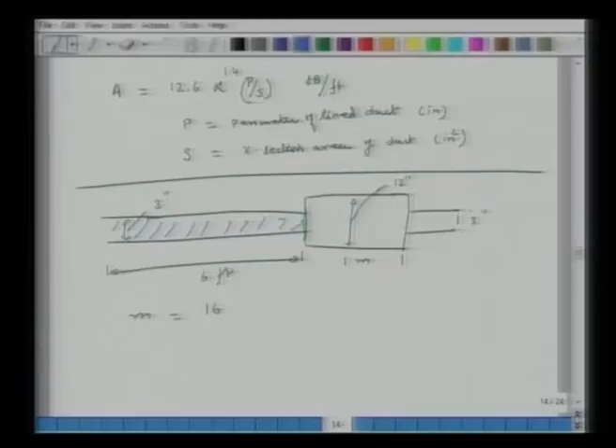So then I said, okay, for comparison purposes, let's say that I line this entire tube with some sort of a highly acoustic damping material, what kind of an impact does it have? So in that case, A equals 12.6 times, and I assumed alpha of 0.08, which is fairly high, times pi d, the perimeter, over pi d square over 4, my area. So if I do the math, what I get is 0.49 dB per foot. So this is roughly 6 feet. So total absorption attenuation will be how much? 3 dB attenuation. So over 6 feet there will be 3 dB attenuation by absorption.